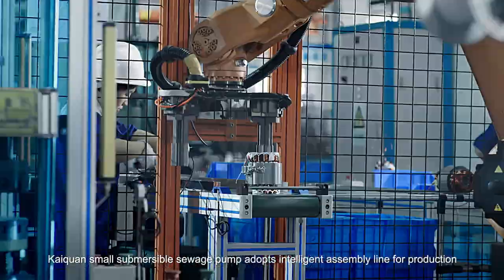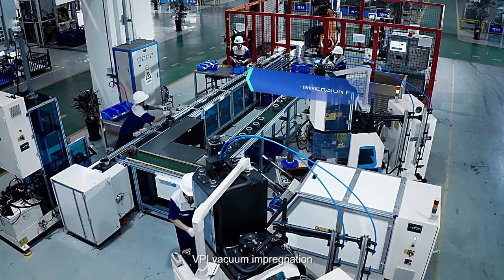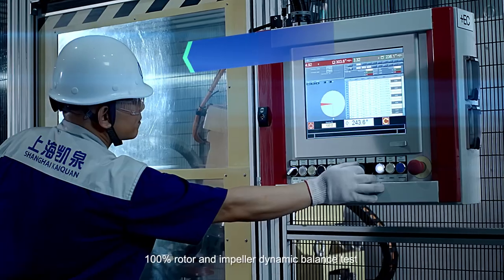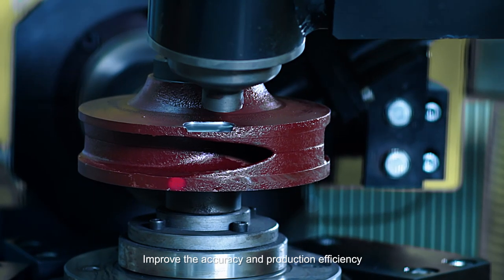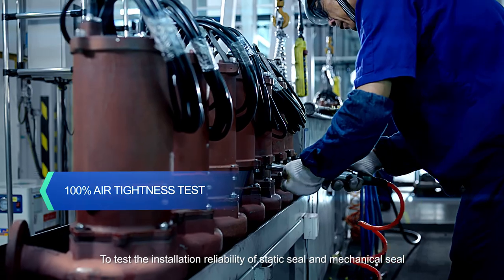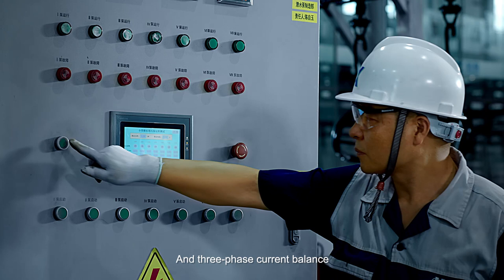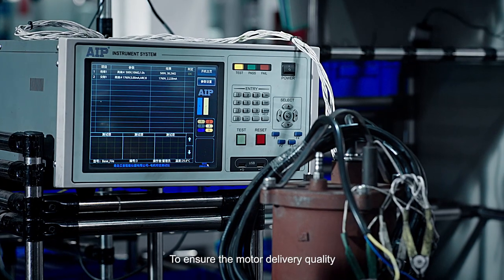Kaiquan small submersible sewage pump adopts an intelligent assembly line for production, including CNC equipment processing, VPI vacuum impregnation, complete machine assembly line equipment and packaging, and various performance tests. 100% rotor and impeller dynamic balance testing, and automatic milling machines imported from Italy improve accuracy and production efficiency. 100% air-tightness testing verifies static seal, mechanical seal installation reliability, and cable tightness. 100% operation testing ensures consistent assembly and three-phase current balance, and 100% motor voltage resistance and insulation testing ensures motor delivery quality.